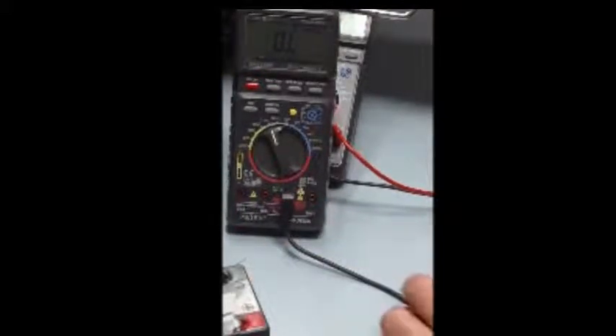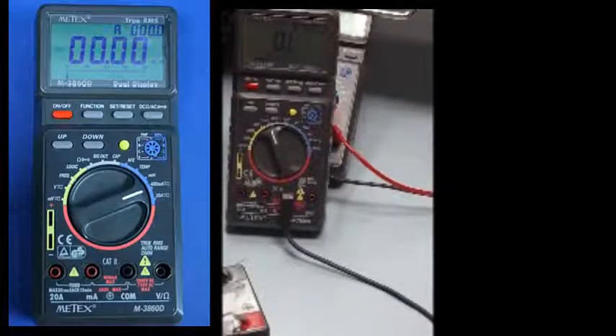This does state that we could read 20 amps. However, I can only read it for a maximum of 30 seconds. I do not want to know much more than that. What we use the multimeter for to read current is to read a very quick short burst. Notice, okay, I've got a current present. If I need a more succinct and robust amount of time for current measurements, we're going to use a lot of different tools, some clamp-on amp probes, some indirect methods that don't require us to get ourselves into a predicament.